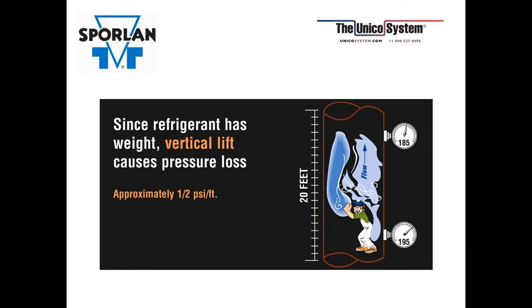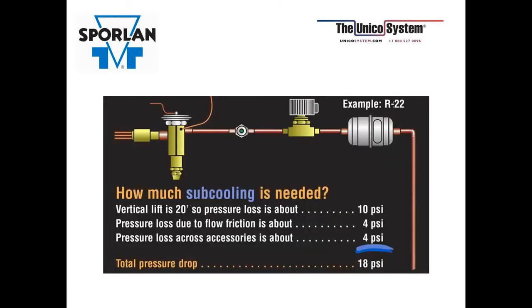And that's a very important thing for everybody to remember, because on the vast majority of our jobs, we have the Unico system up in the attic, with the air handler, and the condensing unit outside, so it's not uncommon to have 20, 25, as much as 50-foot height difference. So this is very important when it comes to charging the systems. In this case, we were showing a 20-foot lift, so that means we have 10 pounds of pressure loss through that vertical lift.